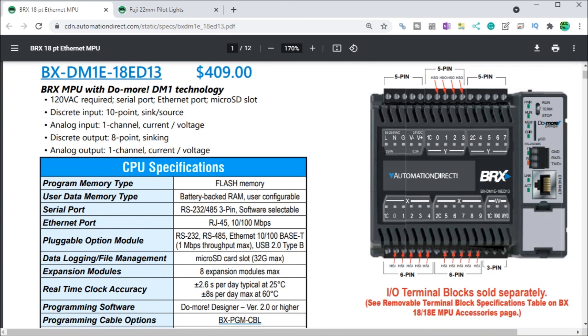Now we have to look at the difference between discrete and analog. Discrete and analog outputs are usually the method to specify the PLC itself. The physical number of discrete and analog outputs helps determine the size or ability of the PLC. Discrete outputs refer to an on/off type that only has two states. Analog outputs refer to a range and express a unit specified by the device — for example, a voltage reference for a variable speed drive like a VFD. A voltage can be sent to the drive to determine the speed or frequency to operate. Analog outputs are usually scaled, which aids readability of the program. In our example, we will scale a variable 0 to 60 hertz to represent a 0 to 10 volt DC signal.